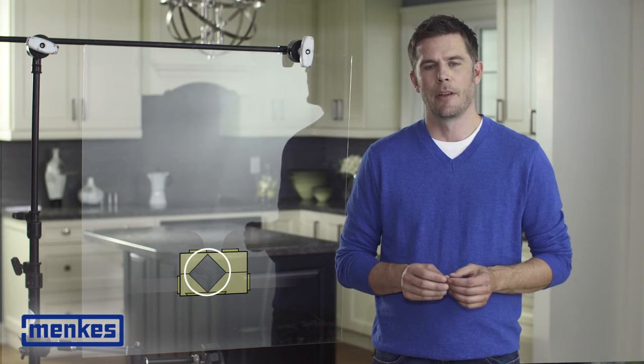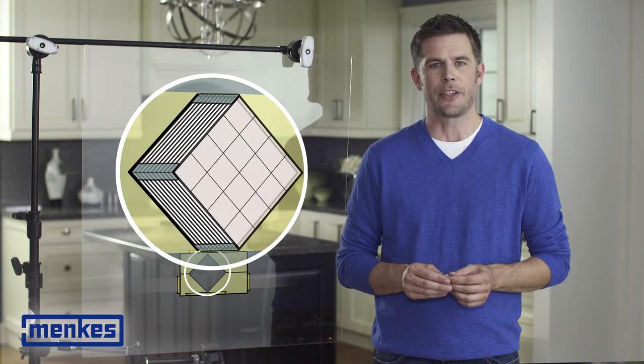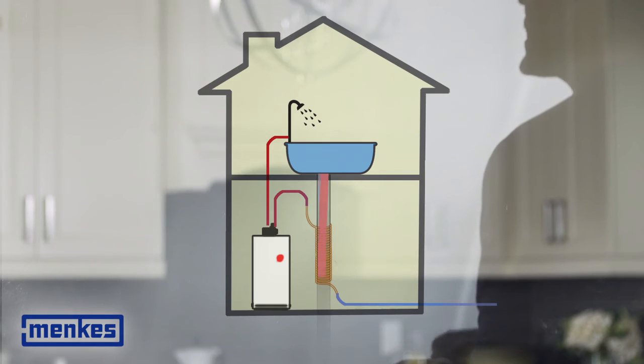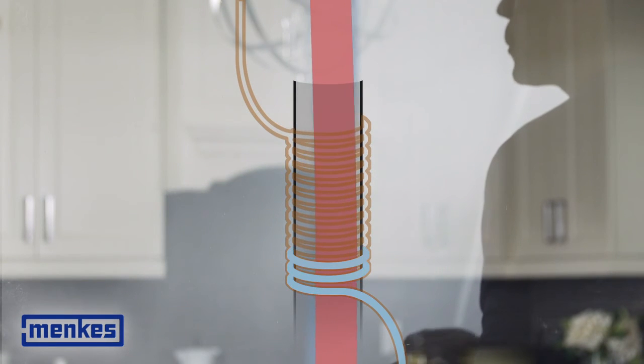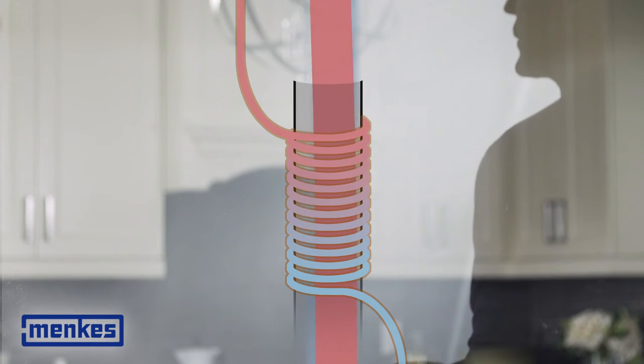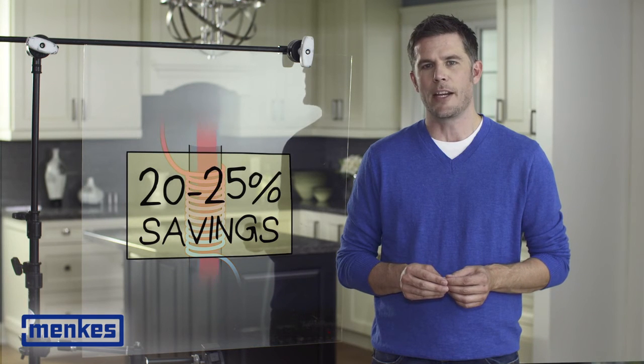Cleaning your HRV is simple — there are filters and a core that need to be washed or vacuumed every three to six months. Drain water heat recovery provides additional energy savings. The large copper coils retain heat when warm shower water falls down the inside of the drain. Incoming cold fresh water flows through the coils and is preheated as it travels to the top of the unit, providing a 20 to 25% savings on domestic hot water heating.